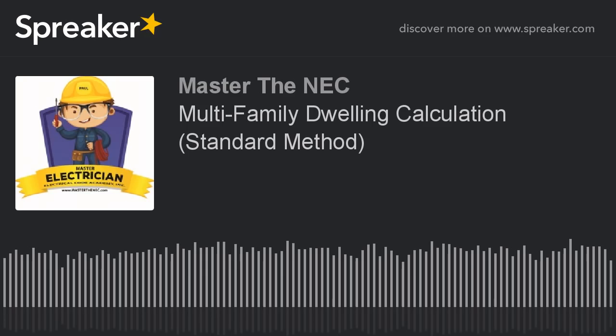It makes that reference after 220.52(A) and (B), so that's why we're using it. So now let's go look at the table for the demand factors in 220.42. Lighting load demand factors. And again, this is including our general lighting and receptacle load.